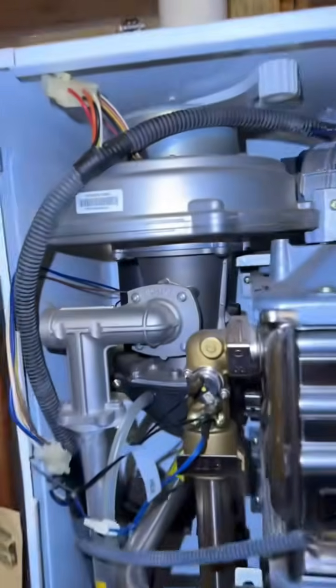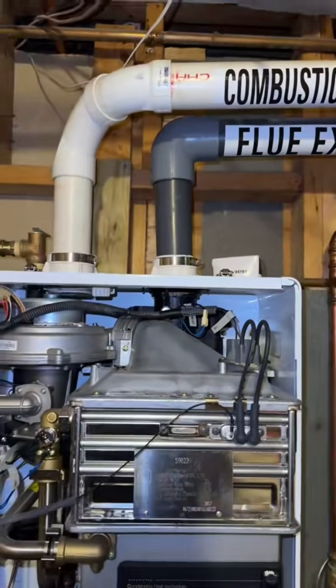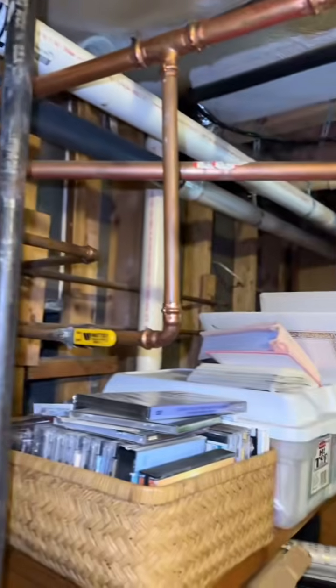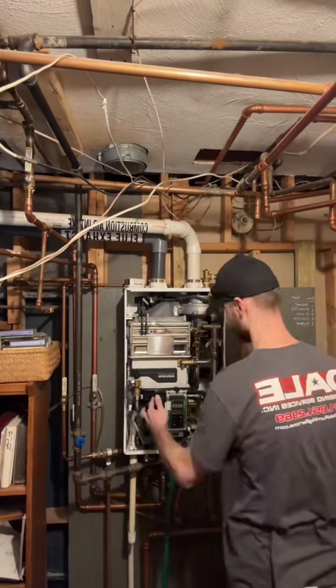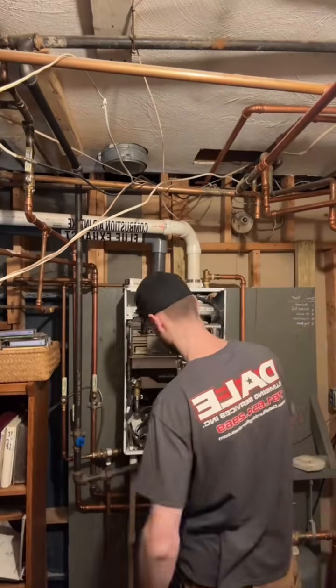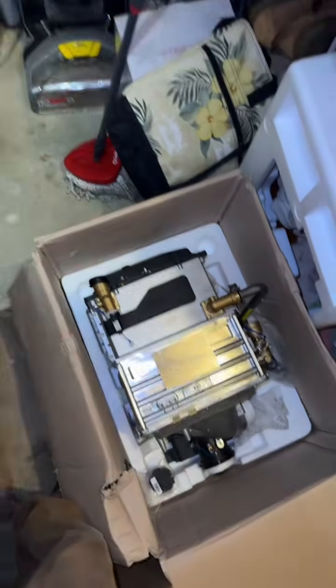This one's leaking flue gas in the cabinet right there, which probably caused this flat plate heat exchanger to fail, and it's leaking gas out of the venturi, all because that flue pipe is crooked.